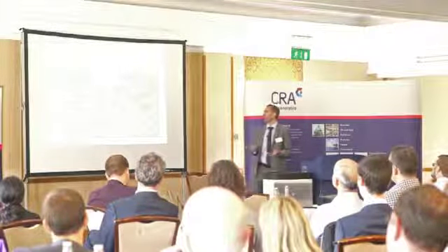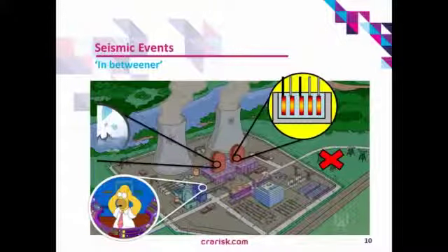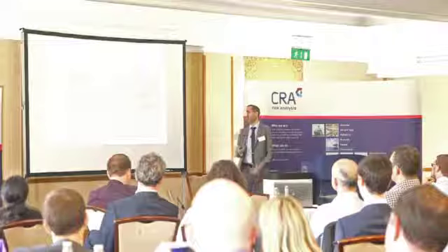You could also have problems in your core in terms of actually inducing a LOCA, so loss of coolant accident from a pipework breach, but also you get pipework breaches all around the plant. So you get a steam line break, feed water break, and some sort of contaminated water is actually not a very good thing.